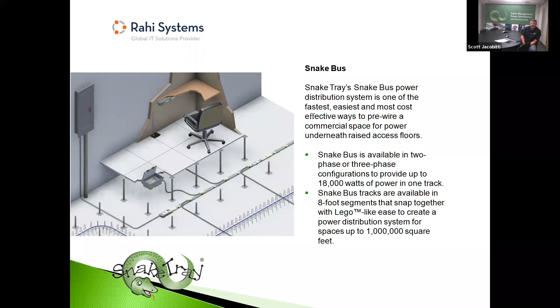The way that the system works is you'll come in from the electrical closet with a 50 amp 3-phase feed into what we call a feed module. And then we have 8-foot tracks that literally snap together like Legos to form what we call almost a linear sub panel below the raised floor. Because remember, we're bringing 50 amps of power in, and each one of those user devices that we're going to install has to have a separate circuit breaker. So everybody's going to be independently controlled. Makes for a much more efficient way to bring power out onto the floor.